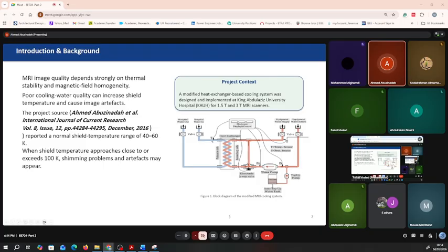The purpose was to separate the dirty water from the clean water and to exchange the temperature without mixing the two loops. It has normal electronic parts like a water pump, an electronic three-way valve, temperature sensors, etc.